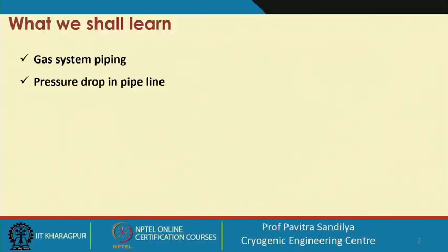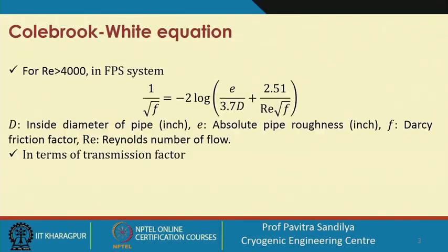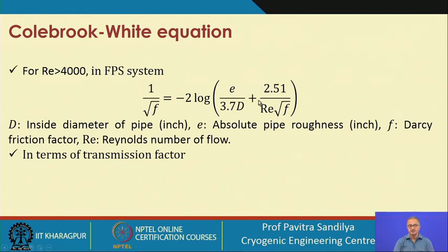We shall be looking into those which are used for natural gas systems. First, we shall see the Colebrook-White expression. In the FPS system, for a Reynolds number more than 4000, it is given by this particular expression. The diameter and roughness factor are given in terms of inches. The first term signifies the roughness effect and the second term signifies the Reynolds number effect. This expression is implicit in friction factor.